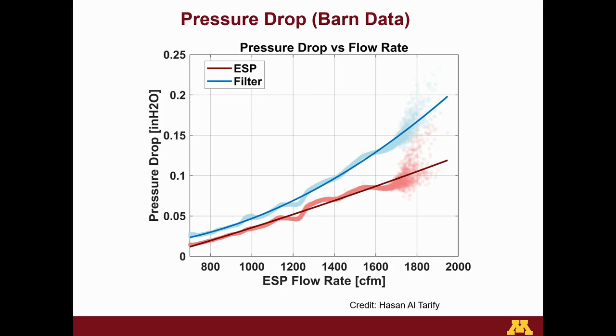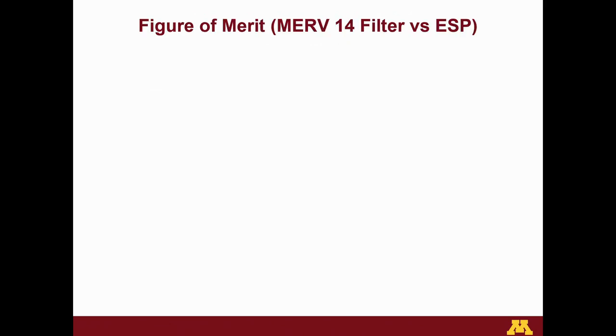Implications being lower energy use, as your fans decrease in CFM moved as static pressure increases, and some work from several years ago from Dr. Tormorell and Yanni, again in engineering. As pressure drop increases, there's more bypass air going into the unit, into the building, and not through the filter or the unit it's intended to pull through.